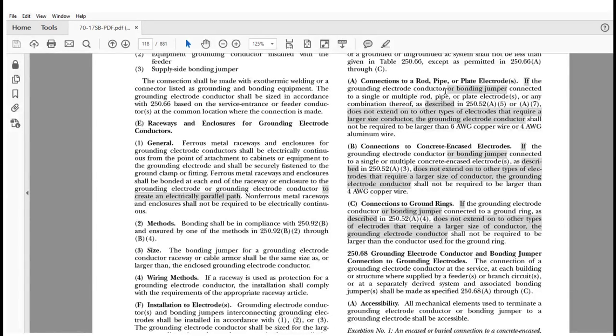If the grounding electrode conductor or bonding jumper, which is connecting multiple rods or plates or pipe electrodes together, to a single or multiple rod, pipe, or plate electrodes or any combination thereof, as described in 250.52 A5 or A7, does not extend on or to other types of electrodes that require a larger size conductor, the grounding electrode conductor shall not be required to be larger than 6. Okay, so let's break it down.